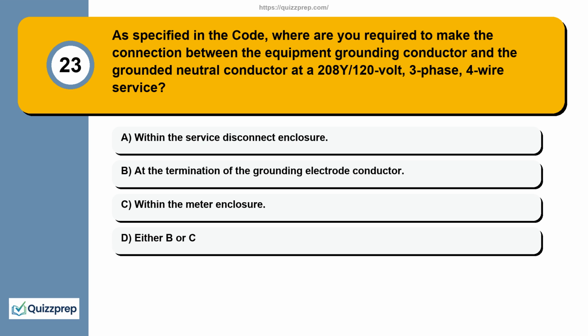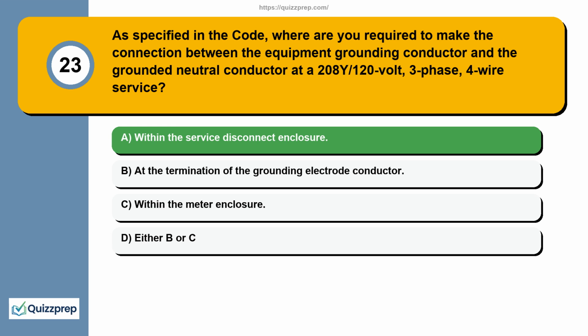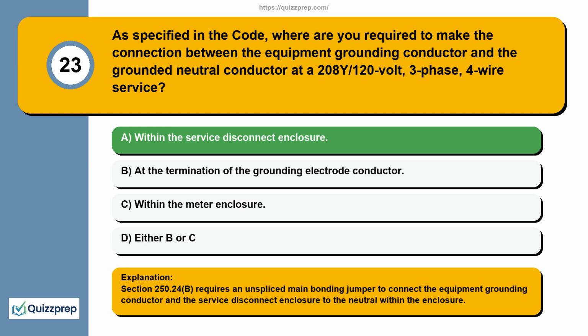Question 23. As specified in the code, where are you required to make the connection between the equipment grounding conductor and the grounded neutral conductor at a 208Y/120 volt, 3-phase, 4-wire service? Within the service disconnect enclosure, at the termination of the grounding electrode conductor, within the meter enclosure, either B or C. Section 250.24 requires an unspliced main bonding jumper to connect the equipment grounding conductor and the service disconnect enclosure to the neutral within the enclosure.